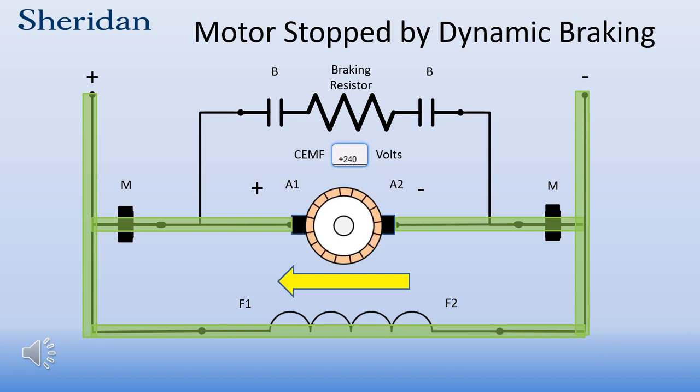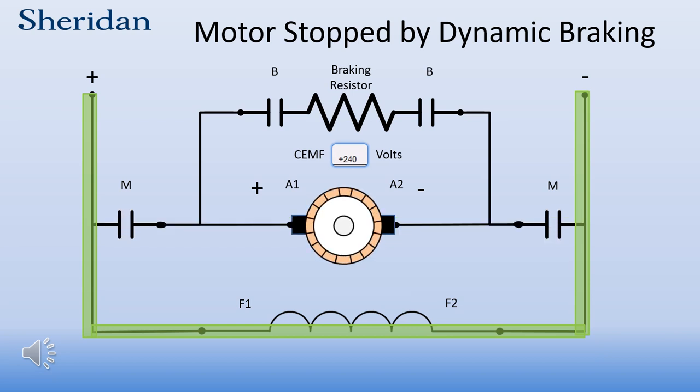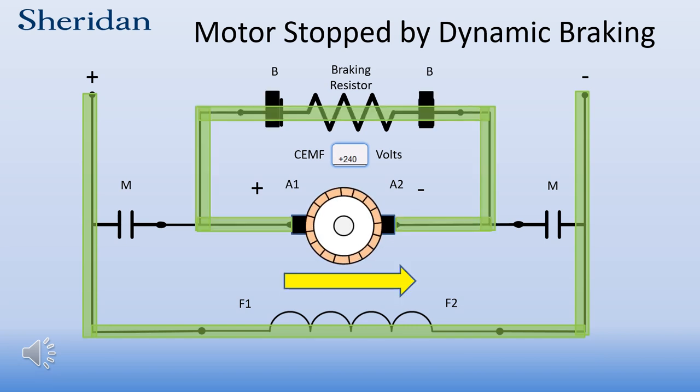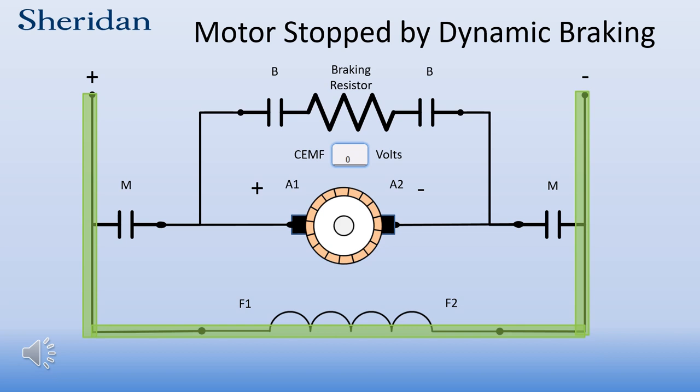With the braking resistor and braking relay contacts installed, when it comes time to stop the motor, the M contacts will open. The armature is still generating a voltage — which was counter-EMF — because it is spinning in the still energized shunt field. When the B contacts close, the resistor is now across the armature. The polarity of the generated voltage is shown near A1 and A2. The armature is now a source of voltage feeding power to the braking resistor. The current now flows in the opposite direction, which causes a torque in the opposite direction that it's turning, and this counter-torque stops the motor quickly.